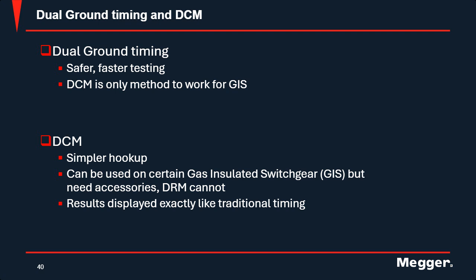So dual grounding, timing, and DCM. We've already talked about how dual grounding is safer and faster for testing. It allows you to work on switchgear such as GIS, and your dynamic capacitance measurement is a simple hookup. It can be used with most types of circuit breakers or circuit switchers, but it is an accessory that you need with your breaker analyzer test set. And then it was also exactly like the traditional timing results.